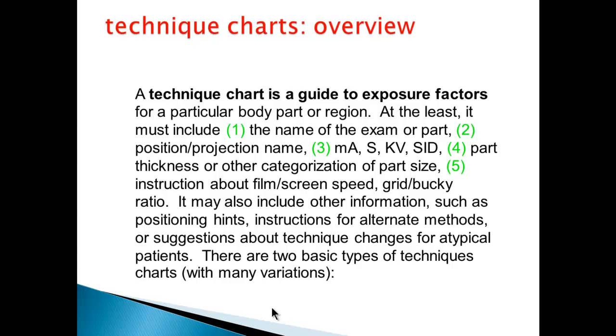A technique chart is usually based on a particular body part, perhaps a region or area, and it could get down to a particular view. It needs to have several parameters: the name or exam, the position, projection if indicated, mA, time, KV, and SID. There may also be categories for film screen speed or grid ratio, remembering that as the grid ratio goes up, so will your exposure.